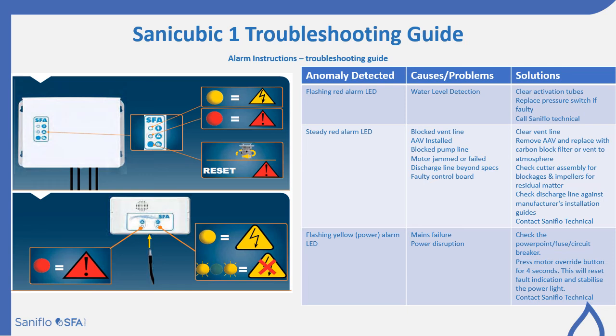If you have a steady red alarm, there's any number of issues through here. It could be a blocked vent line, the AAV could be installed, you have a blocked pump line, the motor may be jammed or failed, discharge line is beyond the specifications, or you have a faulty control board. So a series of things to check through here.